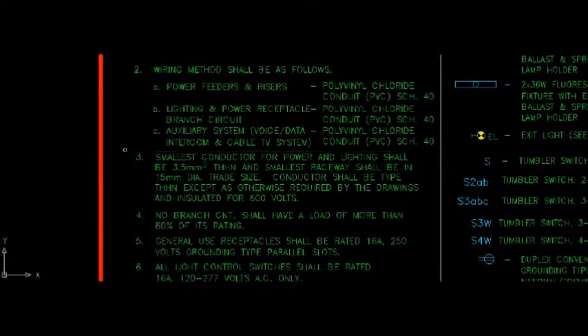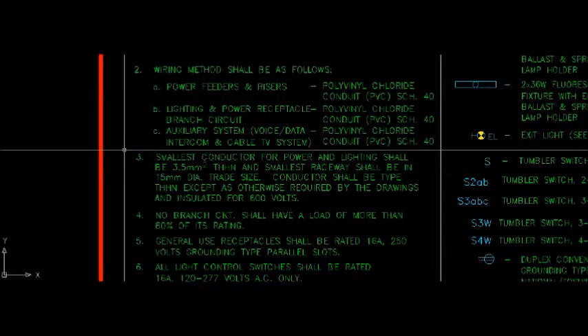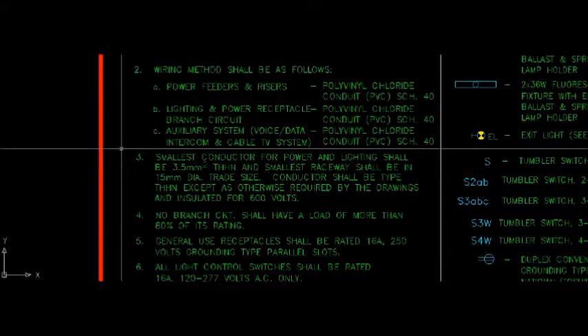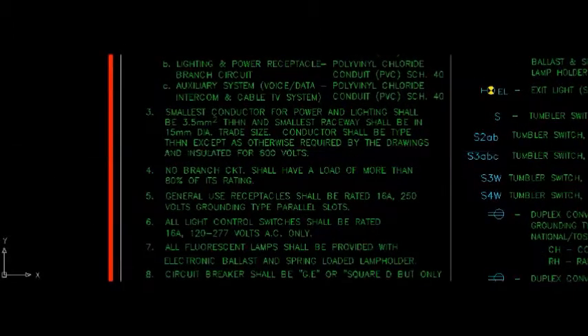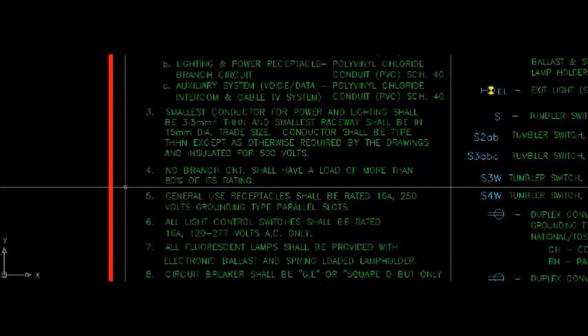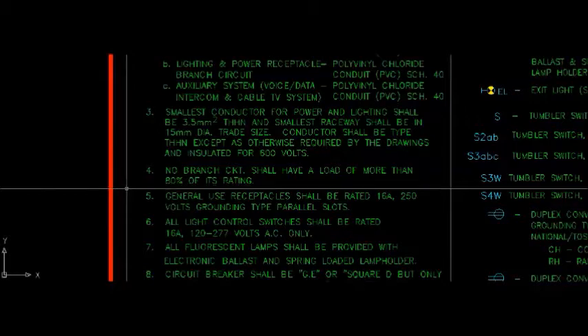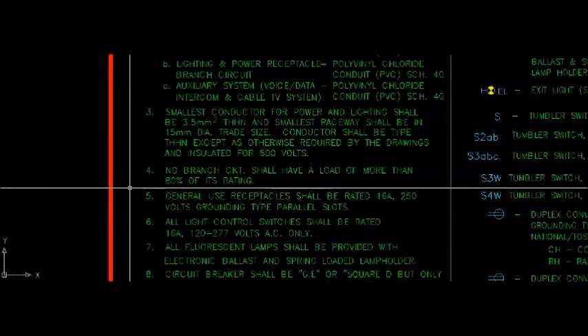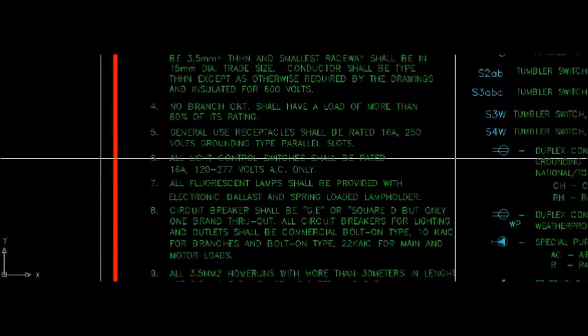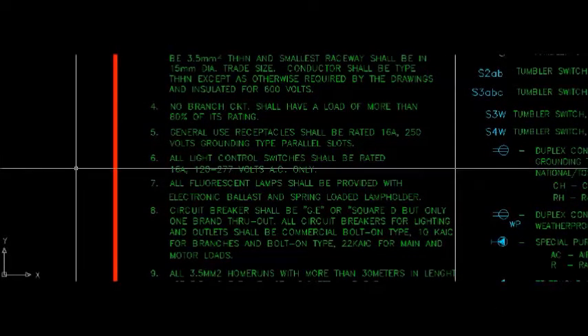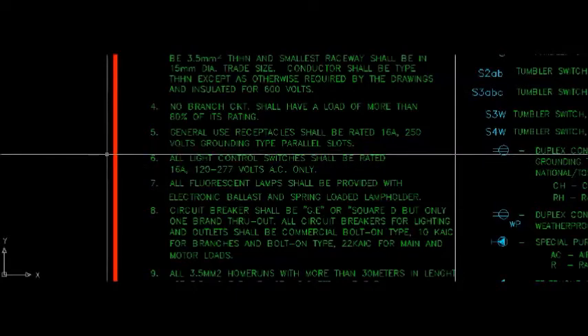Power feeders and risers, PVC SCH40; lighting and power receptacle branch circuit, PVC SCH40; auxiliary, voice or data, intercom and cable TV system, PVC SCH40. Smallest conductor for power and lighting shall be 3.5 mm squared THHN and smallest raceway shall be in 15 mm DIA trade size. Conductor shall be type THHN except as otherwise required by the drawings and insulated for 600 volts. No branch circuit shall have a load of more than 80% of its rating.